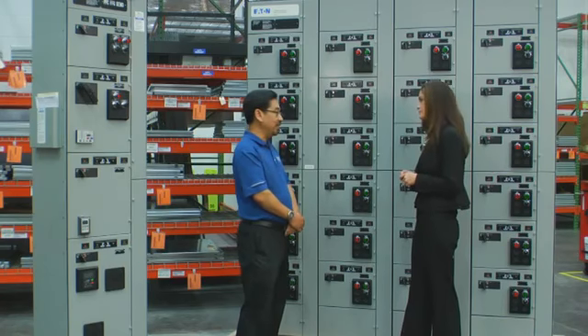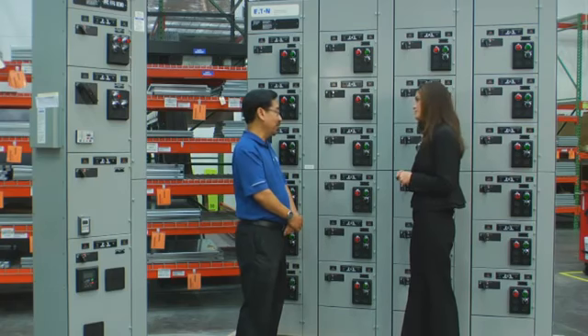But with FlashGard MCC, we've engineered it in such a way that dangerous voltages are not present when human operators are. We already talked about the active interlock system and shutter mechanisms that allow a person to safely insert or remove a FlashGard unit from the MCC cabinet. But equally important is to make sure that operators never have to guess whether the stabs are retracted or extended. Visual indicators on the front panel of the roll-track mechanism allow quick, positive verification of stab position and whether the stabs are connected or disconnected from the vertical bus.